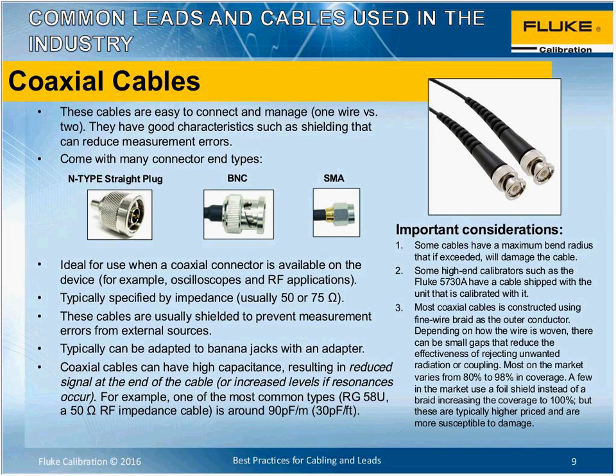If you have a cable that's shielded that you've used forever, it might be due for replacement. So keep that in mind as well. We're going to go through the shielding techniques in a moment, but just note that braided type cables are not as effective as a foil shield. There are some numbers from our training seminar stating about 80 to 98% coverage from outside influences using the braided shield, versus a foil shield, which typically gets 100% if it's in good condition and hasn't been broken inside.